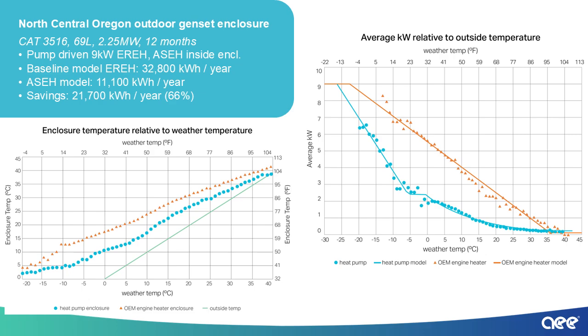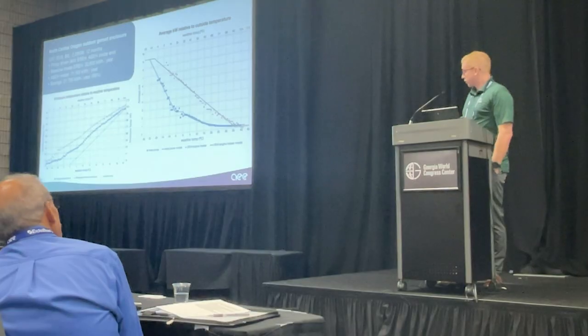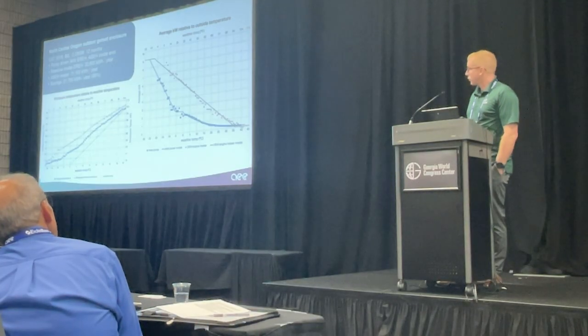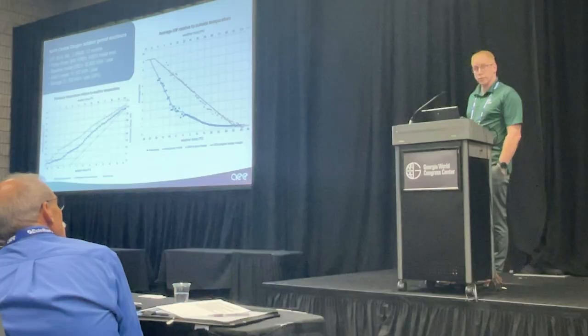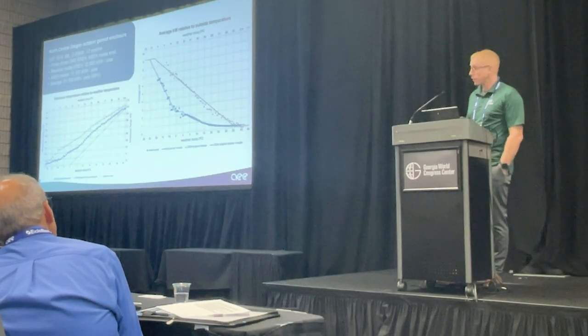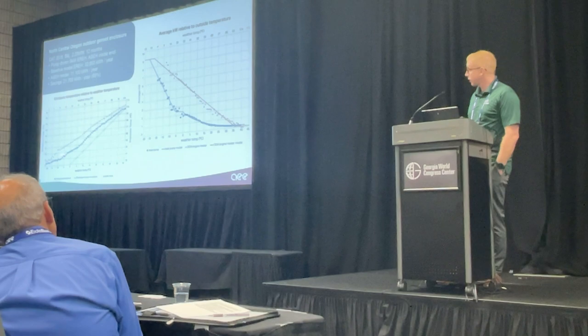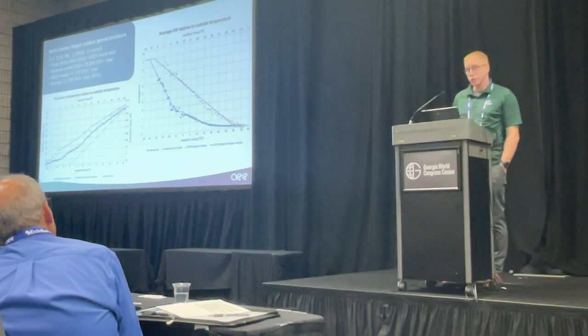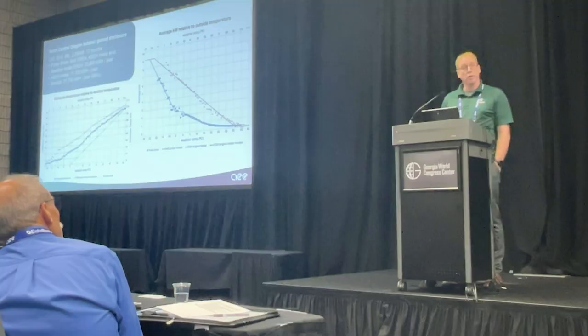The final one was in north central Oregon. In this case, this was 2 side-by-side outdoor enclosures with 2.5 megawatt, 2.25 megawatt gensets. Each of them had a 9 kilowatt electric resistance engine heater, and that was pump driven. You can see one of them had the single speed air source engine heater installed inside the enclosure. The other one was the baseline. You can see that the air source engine heater does reduce the temperature within that enclosure slightly, but the temperature is still above the outside air temperature.